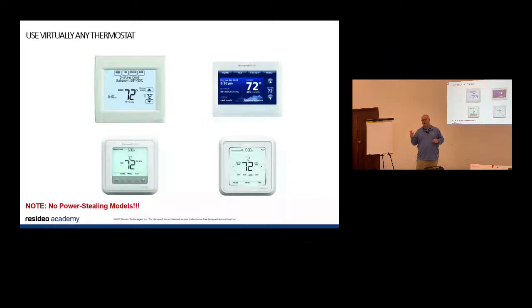But what that does is when there's a call for heat or cool, I'm internally charging that thermostat battery. So I'm always charging it. The problem is if you have a heat only or cool only, half the year that battery's not getting charged. So you come out of whatever season you're in and you come back to like an airplane hangar. I've done one recently. They had Nest thermostats and they didn't know why it wouldn't work. Well, it only had heating. They didn't have cooling. So half the year I'm charging that internal battery. The other half of the year it was going dead. And then I come out of summer to heat that thing back up again and that Nest thermostat's black. It ain't going anywhere.